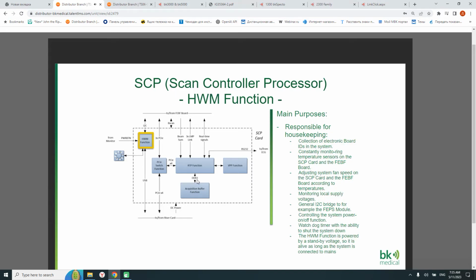The hardware monitor function is responsible for performing different system housekeeping tasks. These tasks include collection of electrical board IDs in the system so that the system software knows the hardware configuration, constantly monitoring temperature sensors on the SCP card and the front-end beamformer board, adjusting system fan speed on the SCP card and on the front-end beamformer board according to the measured temperature, monitoring local supply voltages on the SCP card, functioning as a general I2C bridge to, for example, the FEPS module, controlling or manipulating the system power on and off function, acting as a watchdog timer with ability to shut the system down.